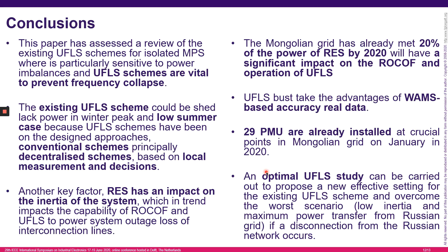However, there is very good news. The Mongolian power system is moving toward low carbon generation, including many installations coming from wind power and PV systems. As a consequence, we are expecting more inertia reduction in the Mongolian power system. However, the good news is Mongolia has already installed 29 phasor measurement units. And we are taking the advantage of implementing a wide area measurement system in order to enable a wide area under frequency load shedding, okay? In a couple of papers, we will make more advances to the TSO in Mongolia, offering the optimal under frequency load shedding settings, and also proposing a wide area measurement system and protection system for under frequency.